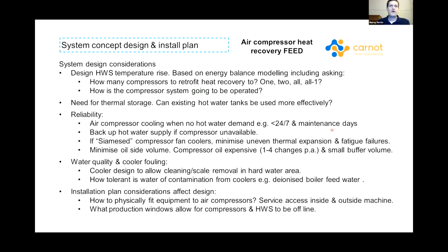So some of the design considerations from that: hot water system temperature rise, what do you actually need the hot water for? Are you going to fit heat recovery to all of your compressors, or to one of them, or to one of them minus your standby machine? Because often you'll have at least a standby machine in your compressed air plant. And as we've talked about, how you're going to operate your air compressor system. If you're only doing a reduced number of coolers, you have to optimize what machines you run so you can recover as much heat as you can. There's no point operating one machine that hasn't got heat recovery on it because you've just wasted your investment.